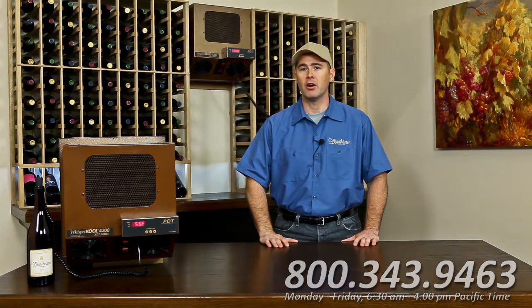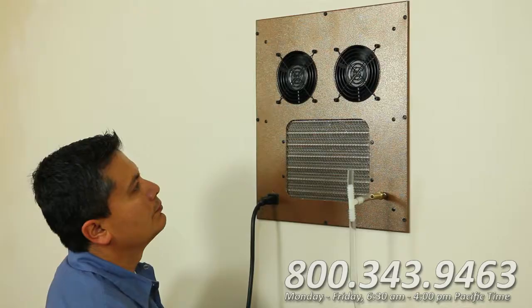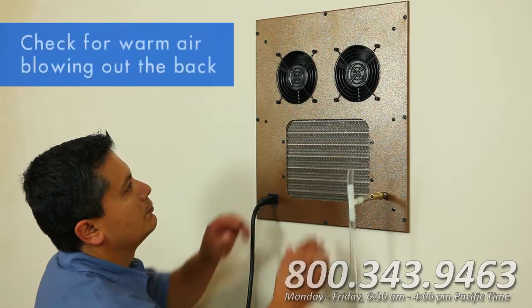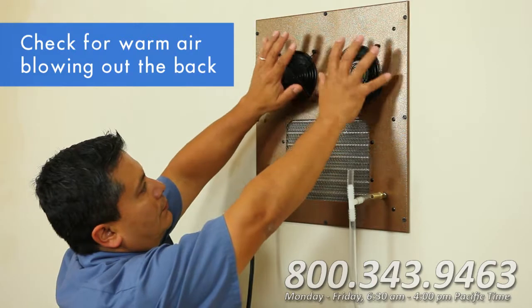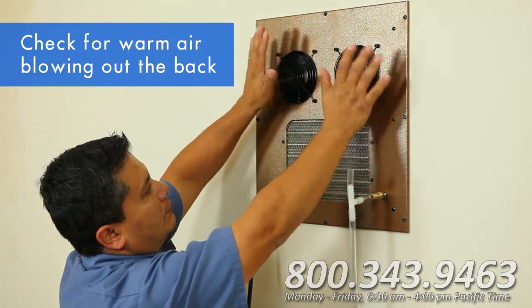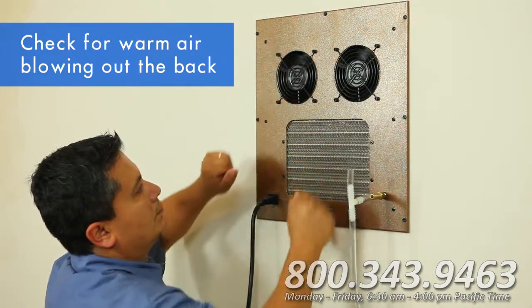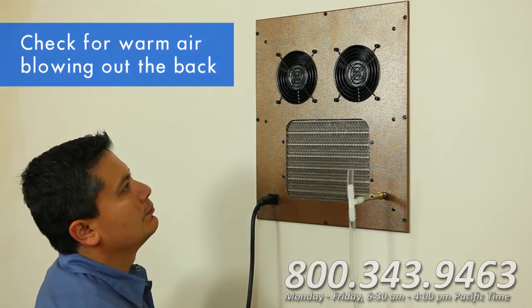Also, check to see if all of the fans are blowing and if they appear to be turning at the same speed. The best way to know if your unit is working is if heat is exhausting out the back side. If you feel warm air blowing out the back, your unit is functioning properly, and you need to consider any installation and ventilation issues.